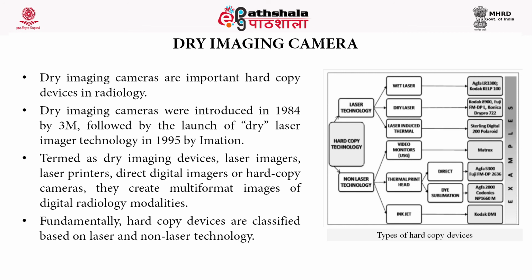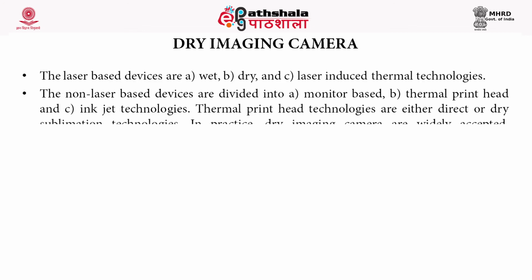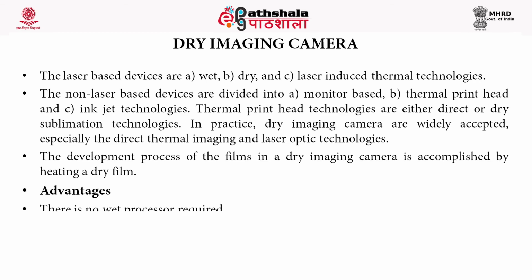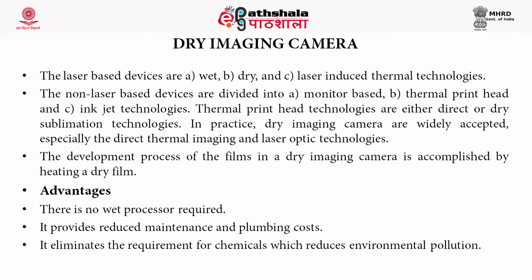Fundamentally, hard copy devices are classified based on laser and non-laser technology. This figure shows the different types of hard copy devices and their classification. The laser based devices are wet, dry and laser induced thermal technologies. The non-laser based devices are divided into monitor based, thermal print based and inkjet technologies. Thermal print head technologies are either direct or dry sublimation technologies. In practice, dry imaging cameras are widely accepted, especially the direct thermal imaging and laser optic technologies.